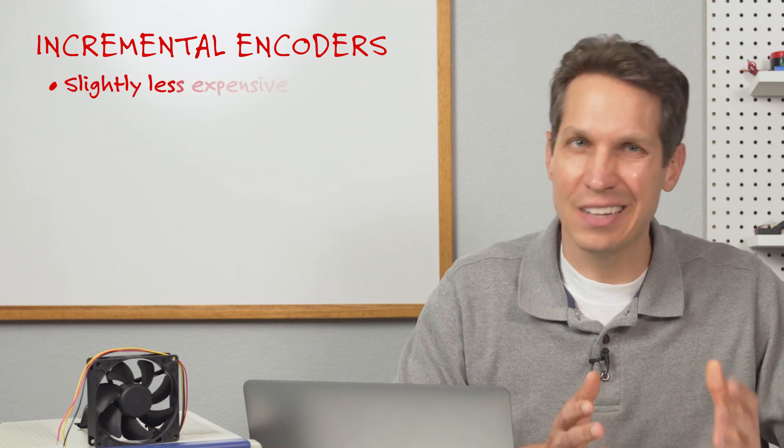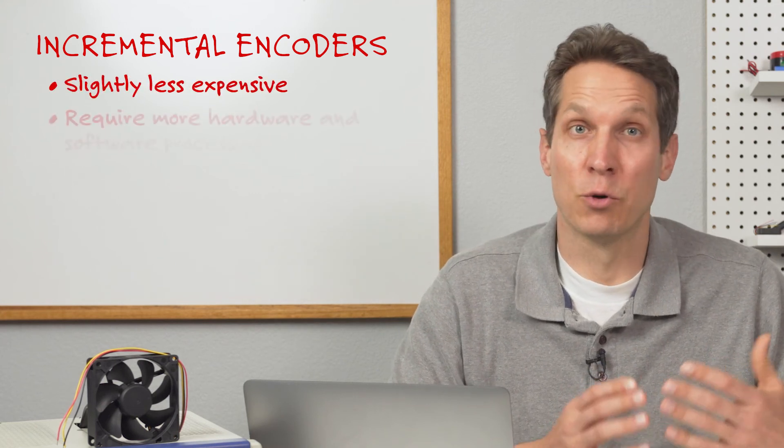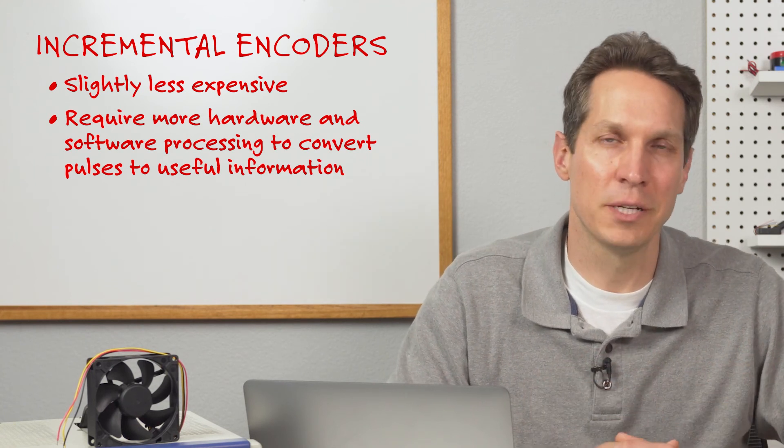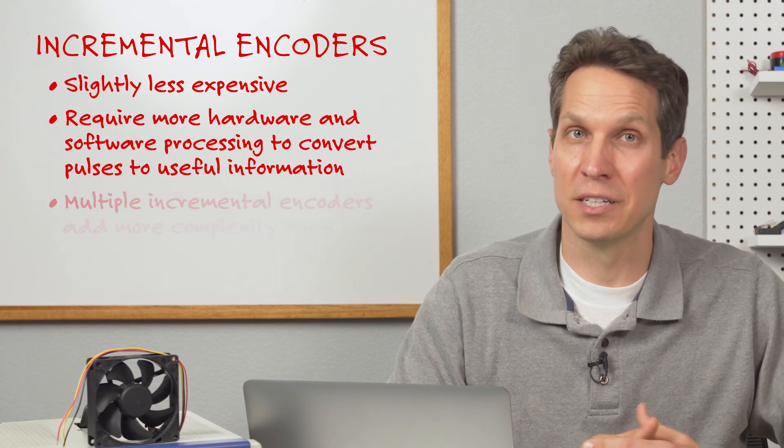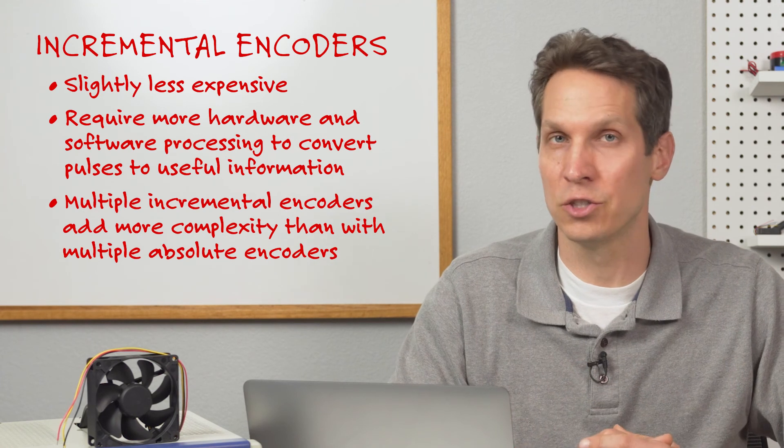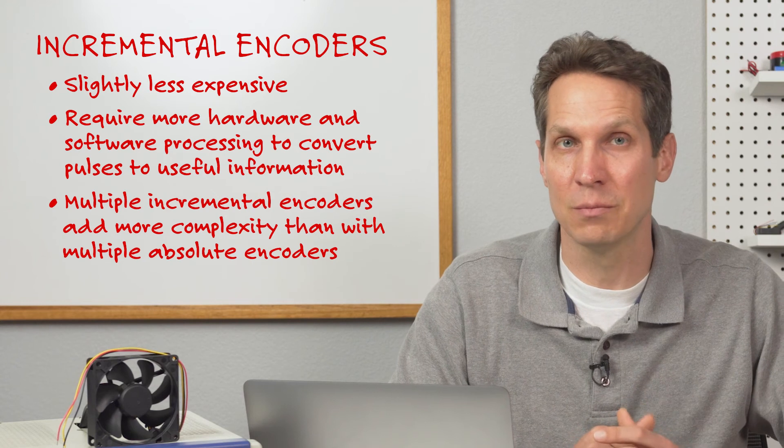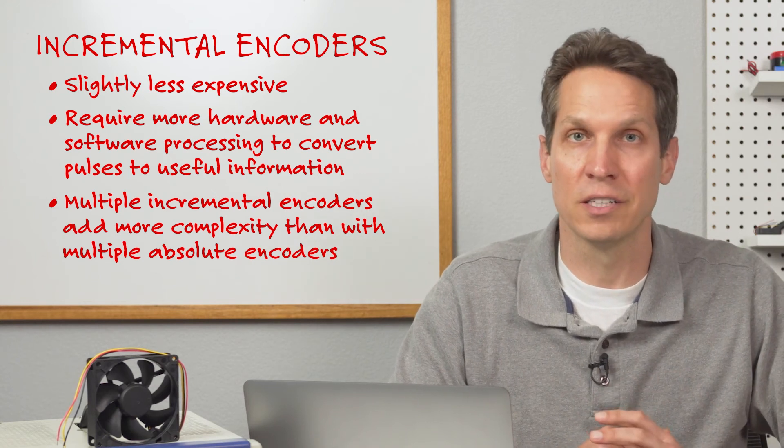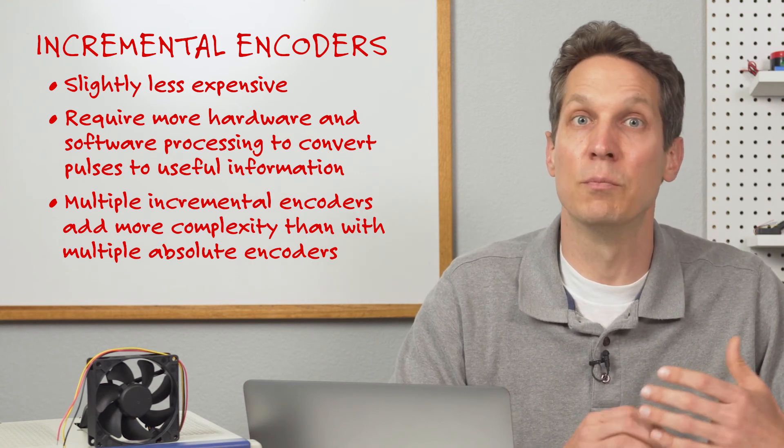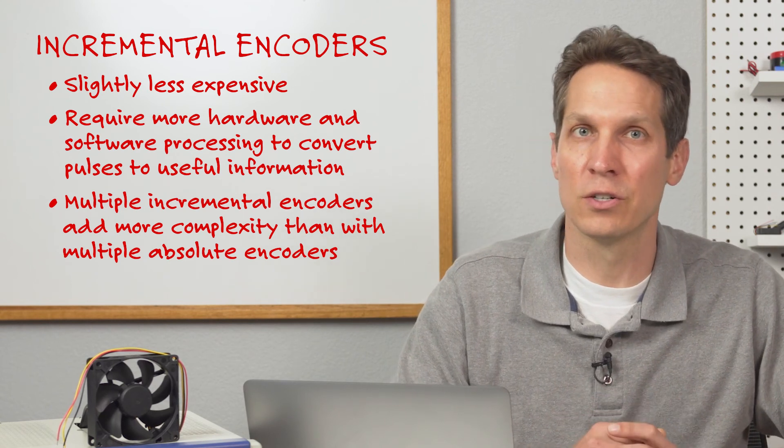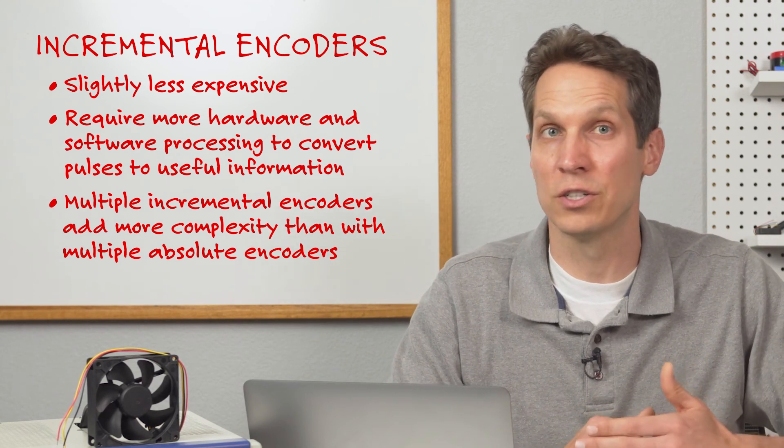While incremental encoders are slightly less expensive, they also require more hardware and software processing to convert the pulses to useful information. This adds even more complexity when you're using multiple encoders in conjunction with each other. It is much easier to combine multiple absolute encoders into the same system with their various serial bus interfaces than it is to put multiple incremental encoders in one system when each incremental encoder requires its own unique quadrature interface.